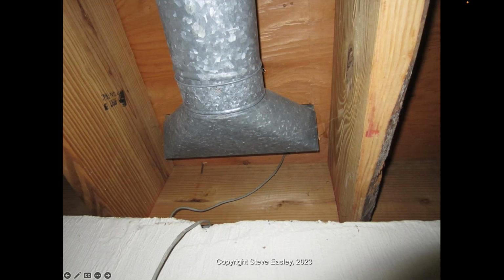So you can imagine if this is in a crawl space, this metal duct is a pretty good radiator. And so that means my register discharge temperatures are going to be lower because nobody took the time to insulate the ductwork. So what we would do here is we want to seal the ductwork with some mastic sealants and then go over that with some insulation. Or you could use a system like AeroSeal, which seals the ductwork from the inside out. It's kind of like Fix-A-Flat.